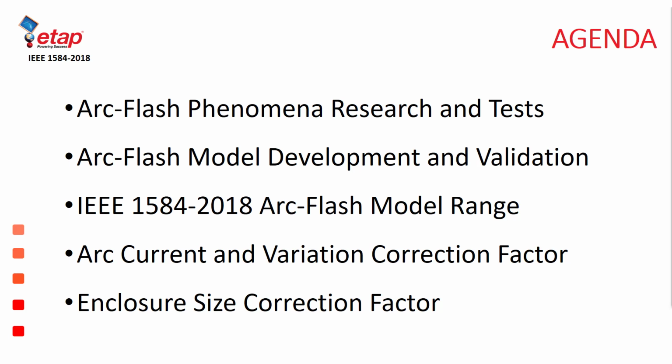After I provide the insights into the model development and validation process, I would also like to describe two of its major capabilities, which are the arc current behavior and the enclosure size correction factors. Of course, the arc current being the key factor to determine the arc fault duration or the operating time of overcurrent protective devices, and the correction factor being important for a more accurate thermal energy calculation.